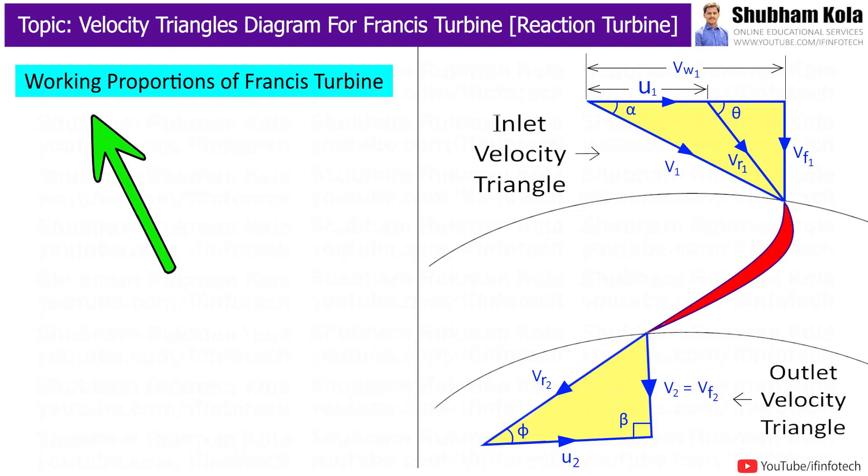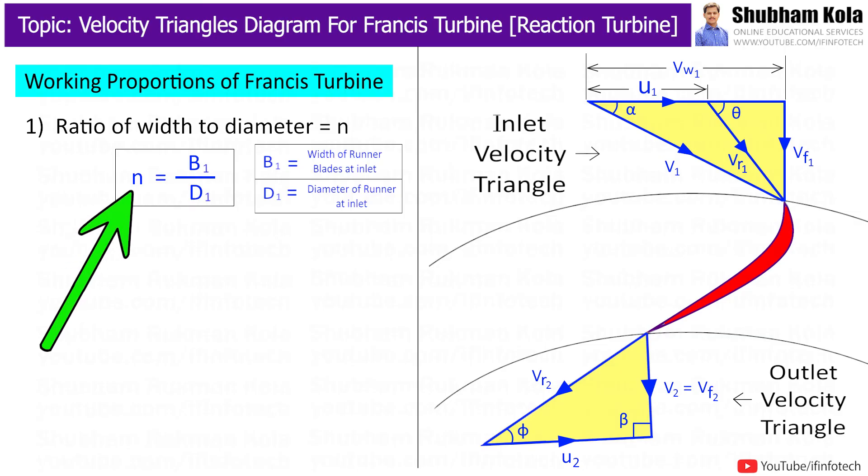Now we will see the working proportions of Francis turbine. In that, first one is ratio of width to diameter, represented by small n. And this value ranges from 0.1 to 0.45.